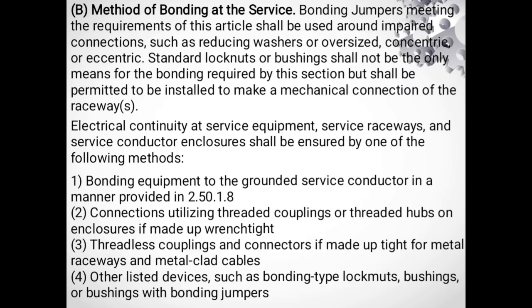Electrical continuity at service equipment, service raceway, and service conductor enclosure shall be ensured by one of the following methods. Number 1, bonding equipment to the grounded service conductor in a manner provided in 2.50.1.8. Number 2, connections utilizing threaded couplings or threaded hubs on enclosures if made up wrench tight. Number 3, threadless couplings and connectors if made up tight for metal raceway and metal clad cables. Number 4, other listed devices such as bonding type locknuts, bushings, or bushings with bonding jumpers.